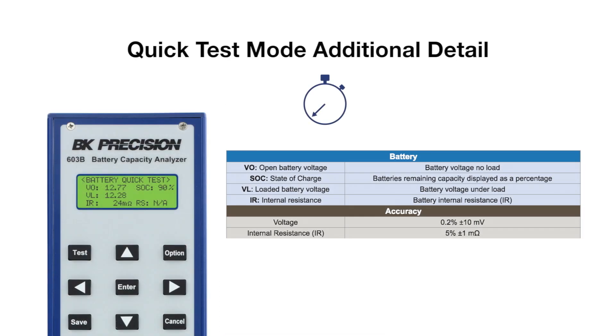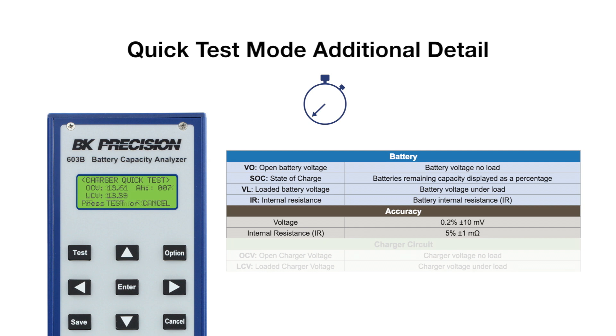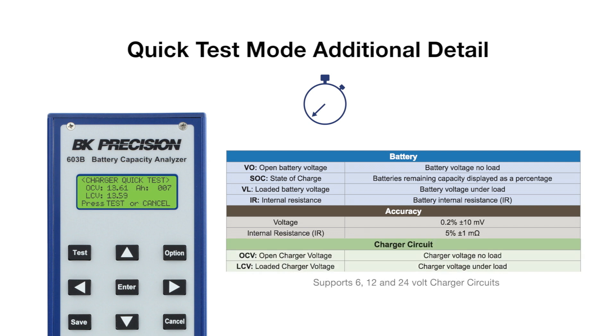Quick Test can be used on both the battery and the charger circuit. Four battery measurement results are displayed in seconds and include open voltage, state of charge, voltage loaded, and internal resistance. Two charger circuit measurements, open and loaded voltage, are displayed when this option is used.